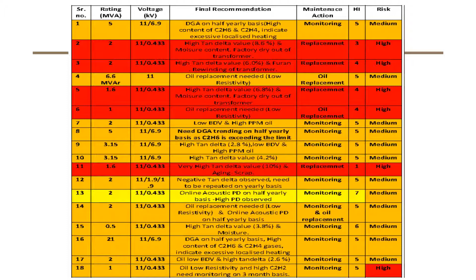Maintenance actions we already discussed in detail. A score of 10 to 8 is good, 7 to 6 is average - that's the band we should operate in. It's a dynamic process - once you do the maintenance actions, the red and yellow zones can be converted back to green zones. A score of 10 to 8 or 7 to 6 with moderate deterioration is okay, but we have to focus on high degradation and high criticality, and take instant action on those.